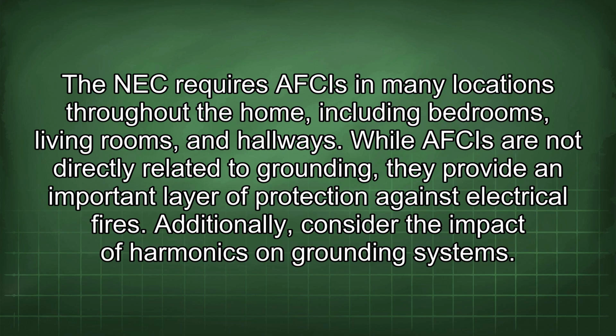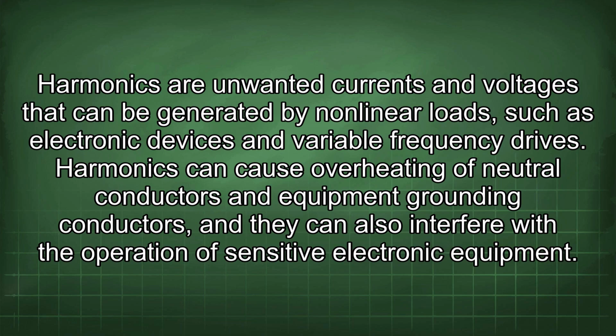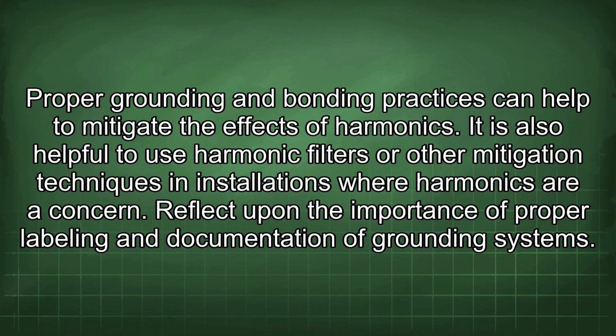Additionally, consider the impact of harmonics on grounding systems. Harmonics are unwanted currents and voltages that can be generated by nonlinear loads such as electronic devices and variable frequency drives. Harmonics can cause overheating of neutral conductors and equipment grounding conductors, and they can also interfere with the operation of sensitive electronic equipment. Proper grounding and bonding practices can help to mitigate the effects of harmonics. It is also helpful to use harmonic filters or other mitigation techniques in installations where harmonics are a concern.